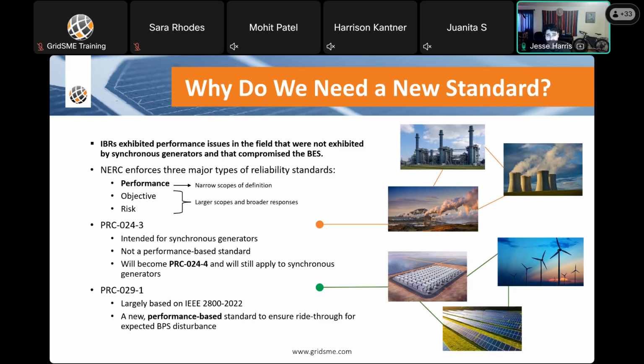So NERC enforces three major types of reliability standards. There's performance, which has narrow scopes of definitions. And then you have objective and risk, which are larger scopes and broader responses. So right now, PRC 24-3, which IBRs fall under, was actually designed and intended for synchronous generators. And it's not a performance-based standard at all. And we will keep that standard. It's going to become PRC 24-4, and it will still apply to synchronous generators. But PRC 29-1 is a standard that was built off an existing IEEE standard, IEEE 2800, and it's a new performance-based standard to ensure ride-through for the expected BPS disturbances.